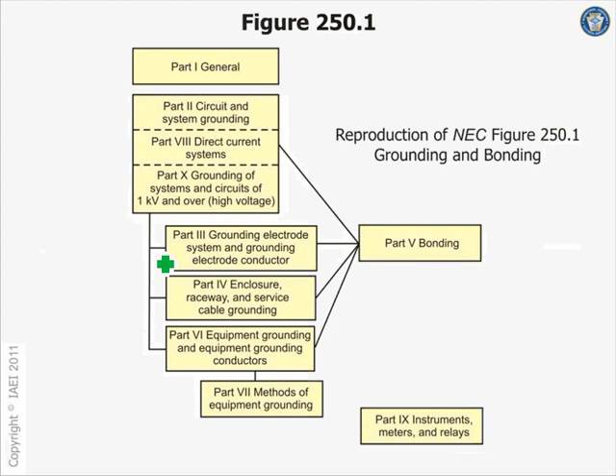Okay, this is just a couple of things, guys, about the layout of the article, Article 250. This talks about general circuits and systems to be grounded. Remember how this is which system you can ground, which system you cannot ground. Systems that you can ground, it's up to you to ground. A system you cannot ground, even if you want to. Talks about it here. DC current, if you guys are into the solar photovoltaic system grounding, this section talks about it. If you're in a high voltage system, the whole section talks about grounding high voltage systems.